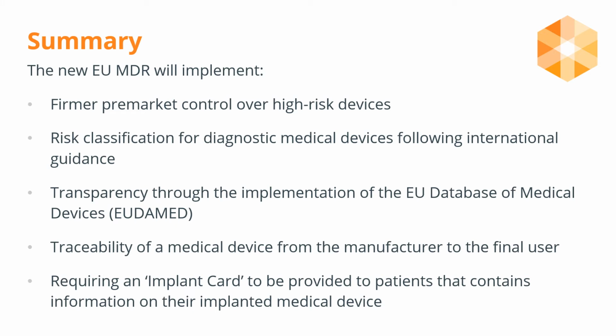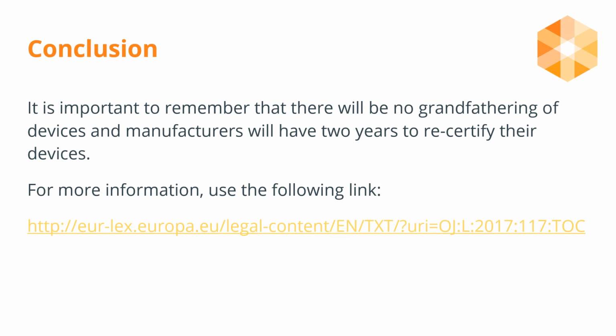In summary, the new EU MDR will implement more control over high-risk devices, changing of risk classification for diagnostic medical devices, increased transparency and traceability, and will require an implant card to be provided to patients that contains information on their implanted medical device. In conclusion, it is important to remember that there will be no grandfathering of devices, and manufacturers will have 2 years to recertify their devices. For more information, please use the link provided.